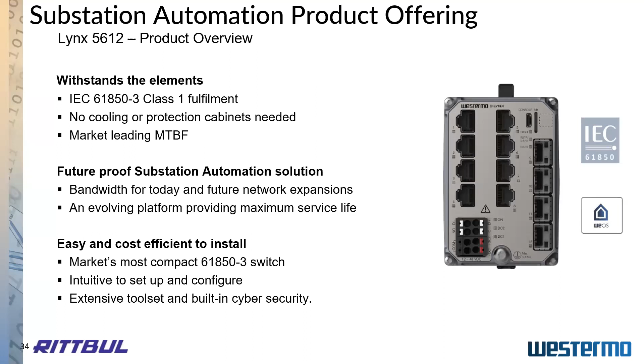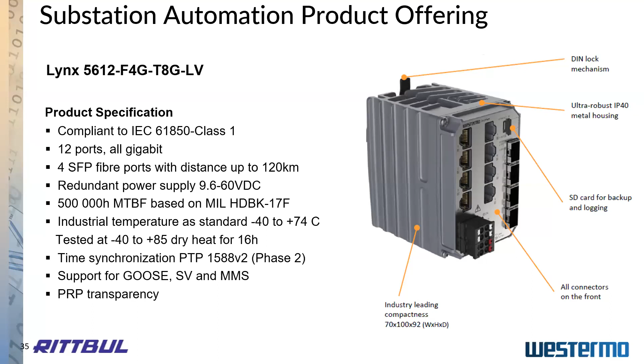Also very similar to the Red Fox, it is compliant to 61850, with 12 ports, 4 of them fiber. It also has a redundant power supply, important, up to 60 volts DC, and a wide temperature range down to -40. These units have actually been integrated in mountainous and remote areas such as Siberia, where temperatures can drop to -40 on a number of days. The Lynx, in perspective, is mainly for protective areas where requirements are maybe not as high, but it is 61850 approved and can be integrated into that type of environment.